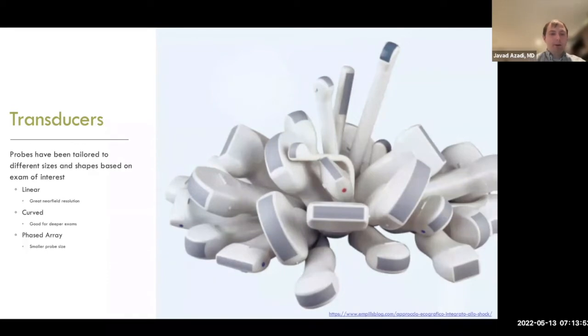And then finally, there are phased array probes, and these have a smaller probe size. They're specialized. They can uniquely arrange the piezoelectric elements so that you can get into a small space, you can steer, and you can image things you otherwise wouldn't be able to see. So examples would be transesophageal echo, right? The echo is in the esophagus, or transvaginal ultrasound or transrectal ultrasound, where you have tighter spaces. But the engineering in these is fantastic. The one takeaway from this is, as the resolution improves, the depth decreases. So higher frequency probes will have better near field resolution, but they can't go as deep, and that's because the sound waves are dampened as they go deeper and deeper.